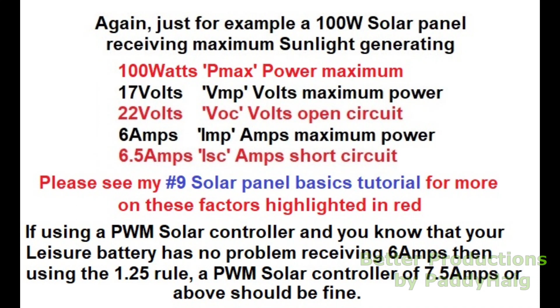Another example, using a PWM solar controller, would be a 100 watt solar panel. When receiving maximum sunlight, according to its documentation, it creates 6 amps IMP at 17 volts. The PWM solar controller can trim the voltage down to the required battery charging level, and that voltage may be adjusted by some programming interface built into the device. However, the amps or current can't be adjusted on PWM controllers. The 6 amps IMP should be multiplied by the 1.25 rule. 6 times 1.25 equals 7.5 amps. So the very minimum amperage handling ability of the PWM solar controller you'd want for this 100 watt panel would be 7.5 amps or above, probably around a 10 amp model.